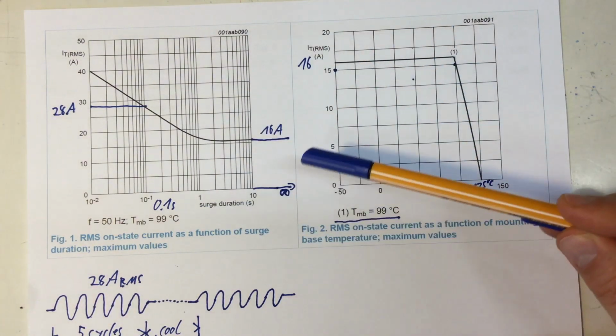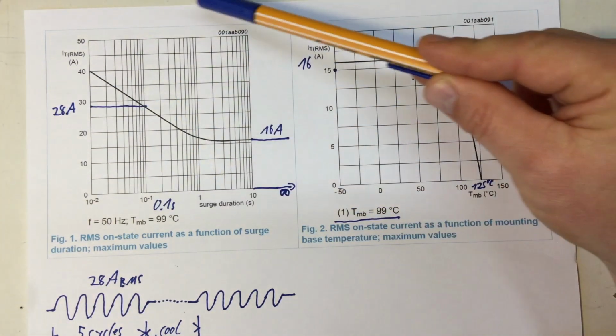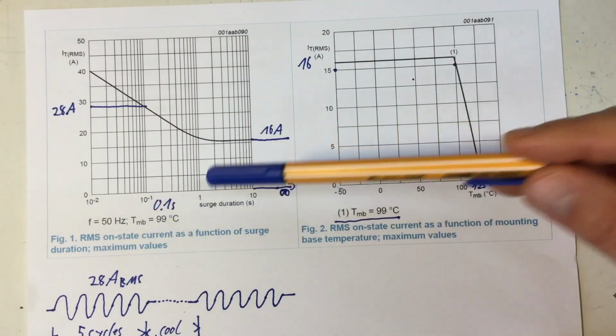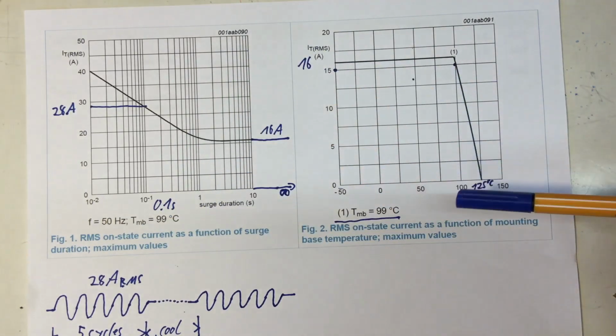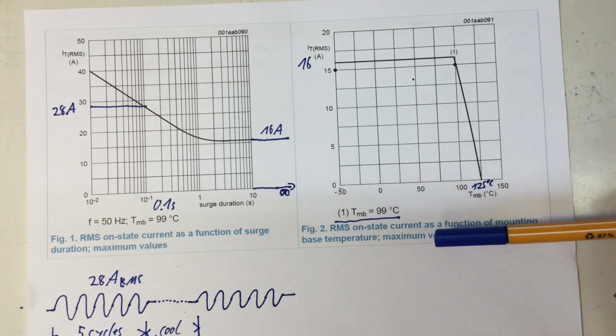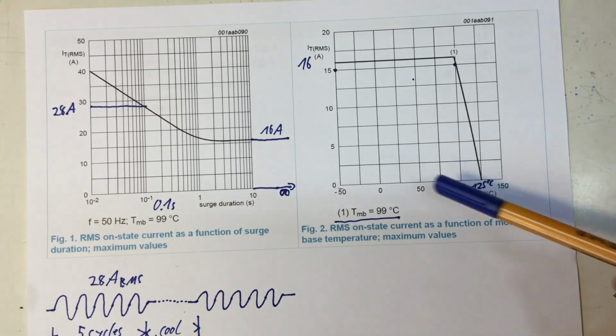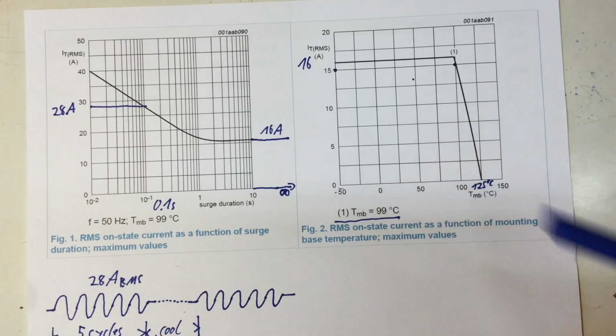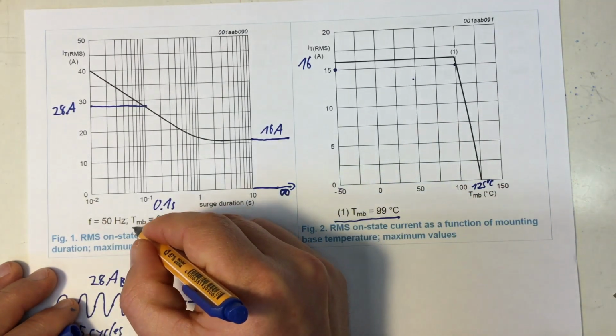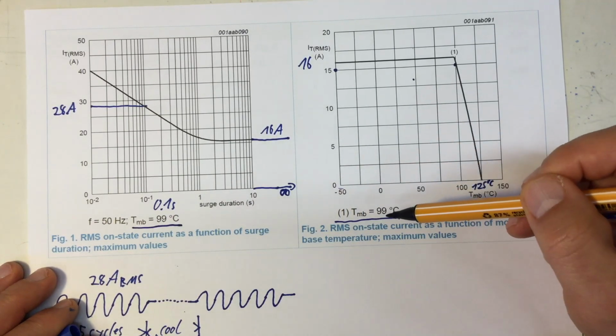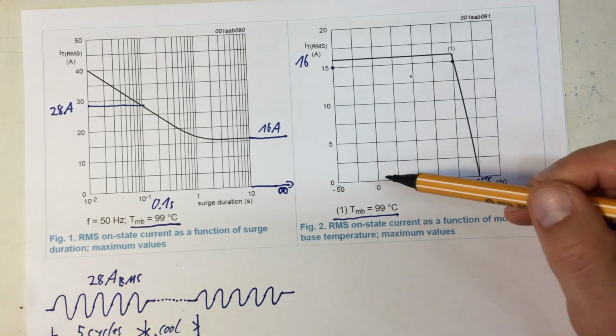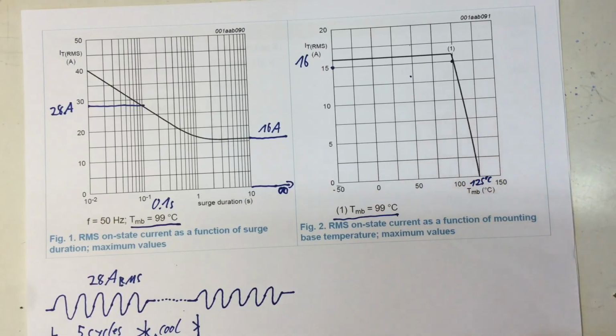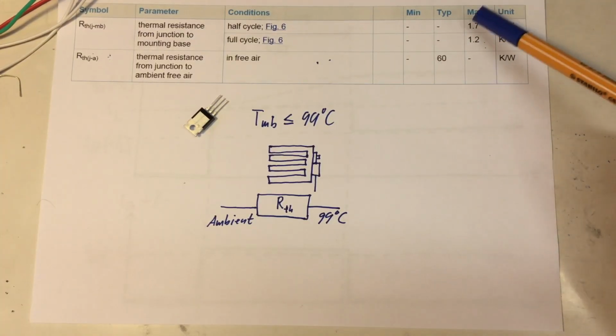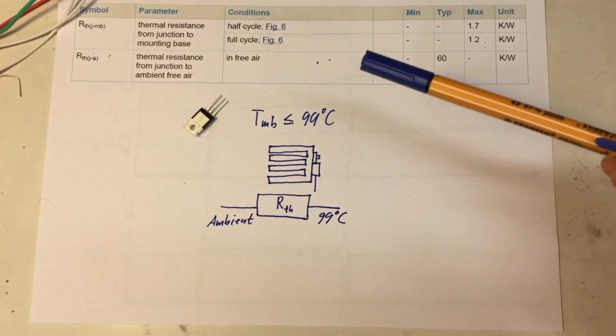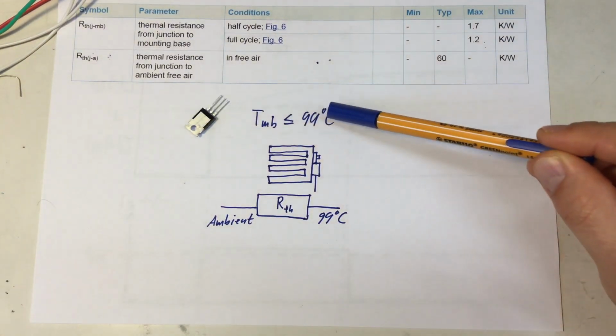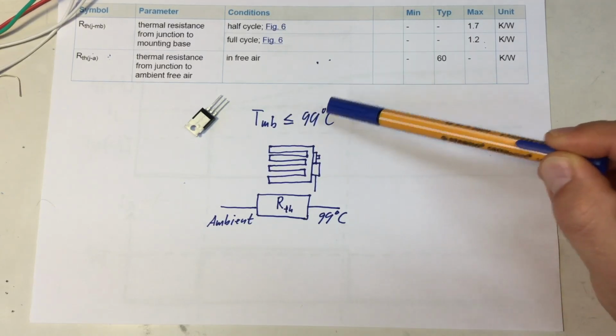If we go a little bit back, we see that many of the graphs—here's on-state current as a function of surge duration, and maximum RMS on-state current—are all given for a mounting base temperature of 99 degrees Celsius. So, in theory, you don't have to work with these values here, as long as you make sure that the mounting base of your TRIAC doesn't get hotter than 99 degrees Celsius.